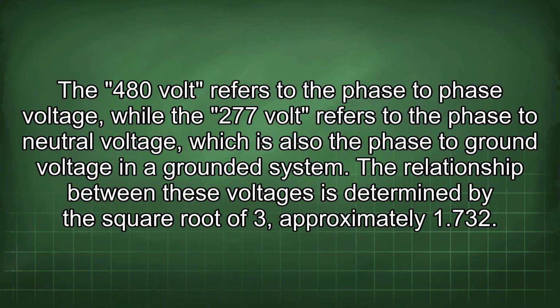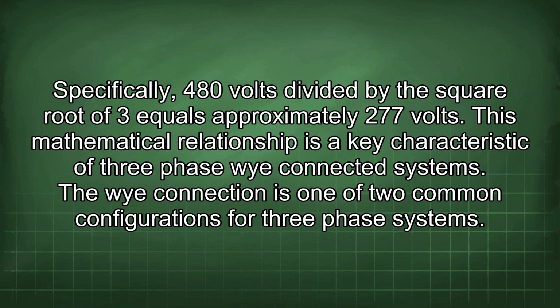The 480 volt refers to the phase-to-phase voltage, while the 277 volt refers to the phase-to-neutral voltage, which is also the phase-to-ground voltage in a grounded system. The relationship between these voltages is determined by the square root of 3, approximately 1.732. Specifically, 480 volts divided by the square root of 3 equals approximately 277 volts. This mathematical relationship is a key characteristic of three-phase Y-connected systems.